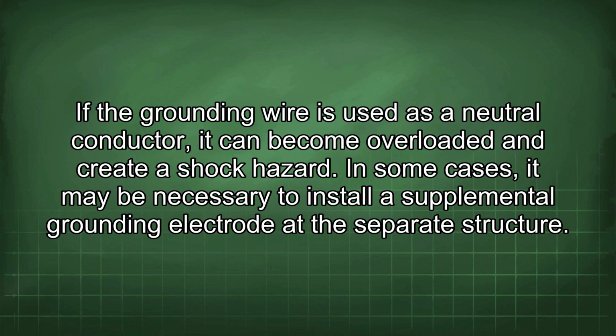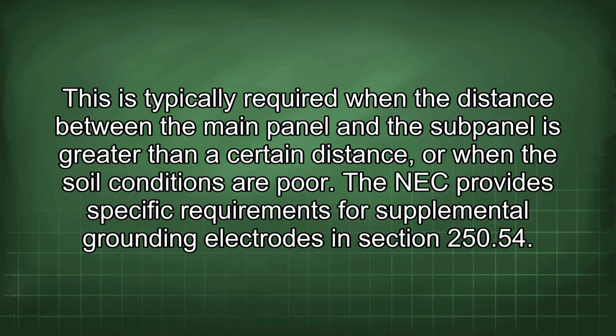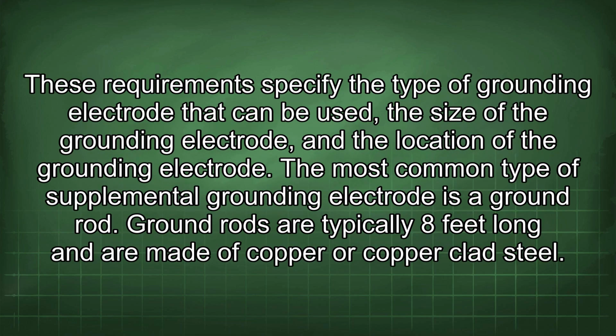In some cases, it may be necessary to install a supplemental grounding electrode at the separate structure. This is typically required when the distance between the main panel and the subpanel is greater than a certain distance, or when the soil conditions are poor. The NEC provides specific requirements for supplemental grounding electrodes in section 250.54. These requirements specify the type of grounding electrode that can be used, the size of the grounding electrode, and the location of the grounding electrode.